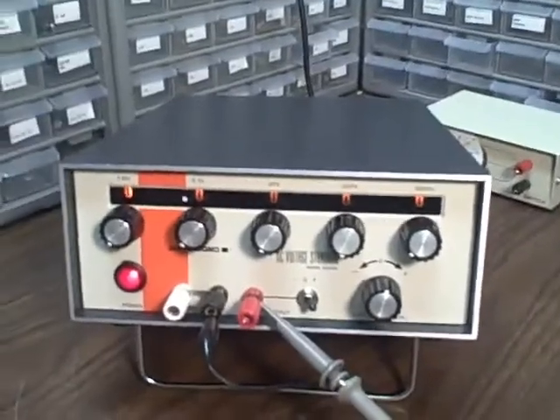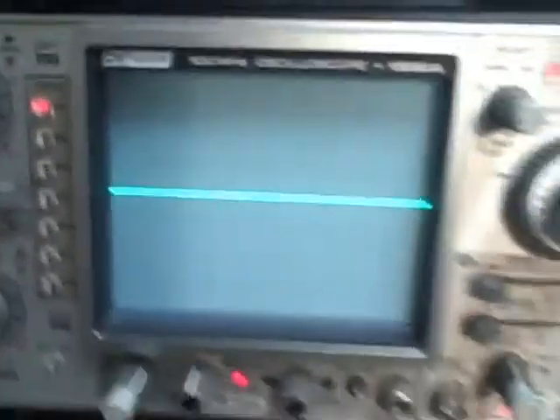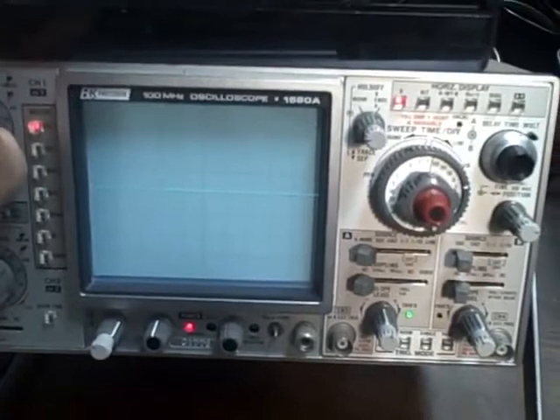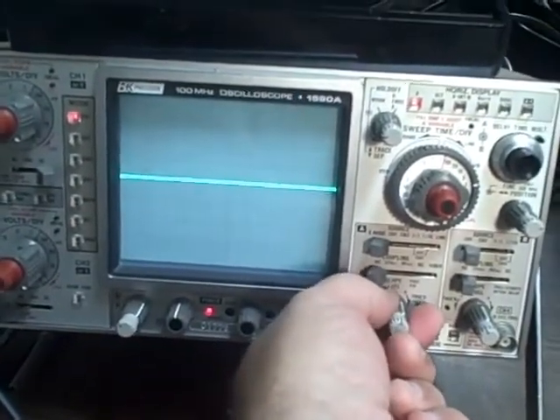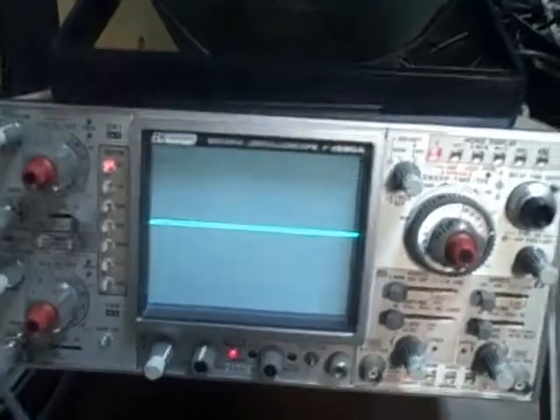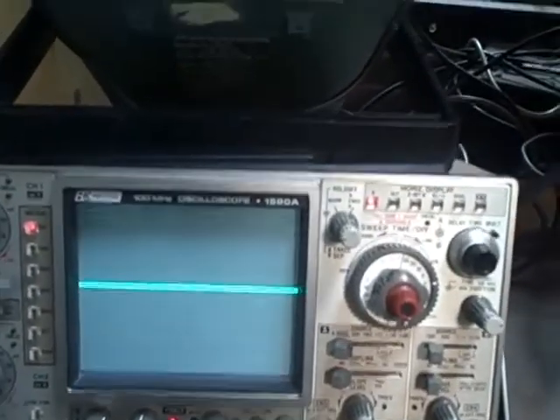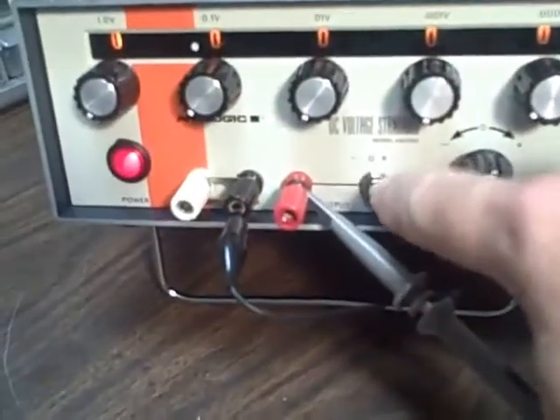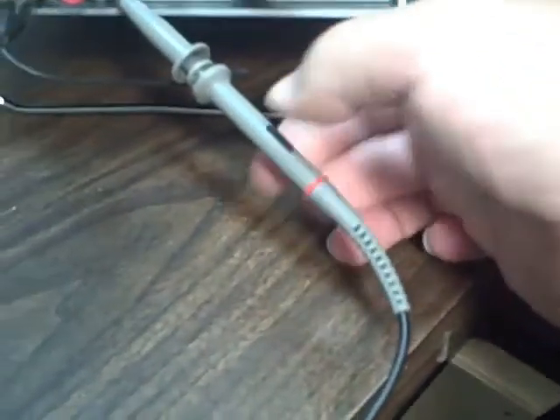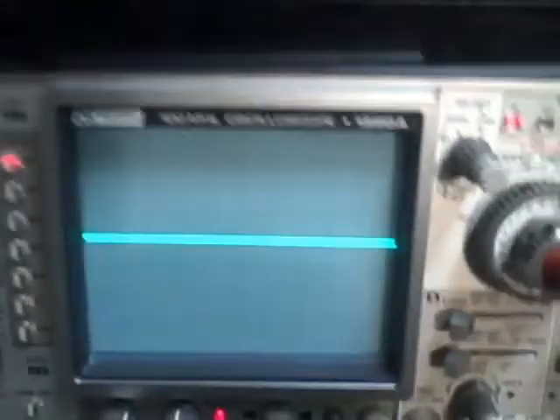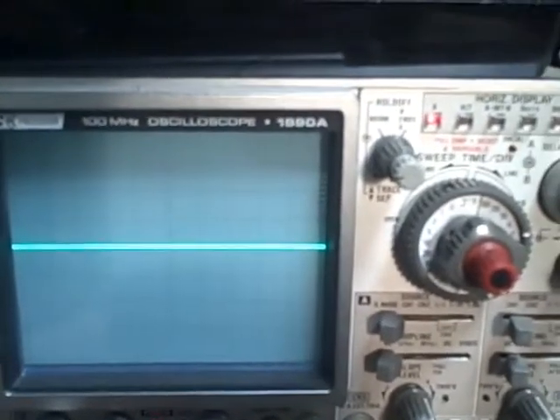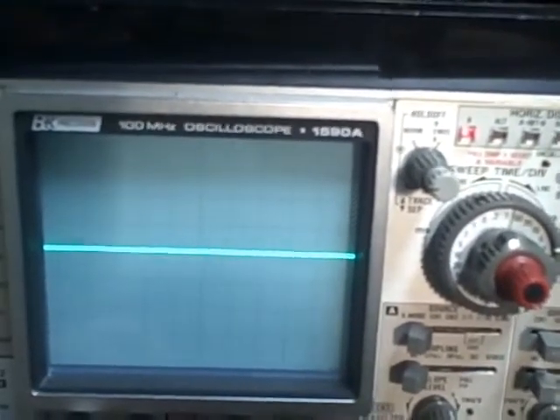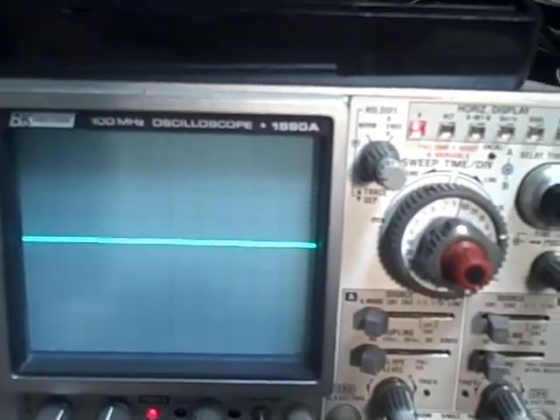And let me give you a look at this. Right now the output is on a B&K scope, and I will put the scope on the absolute lowest position. We are on 5 millivolts per division, and I do have the standard on. My probe is on the ×1 position, so I am feeding a signal directly into the scope. On my most sensitive setting, I cannot see an observable disturbance on this line. It's clean. And I can change the frequency, it really doesn't matter.